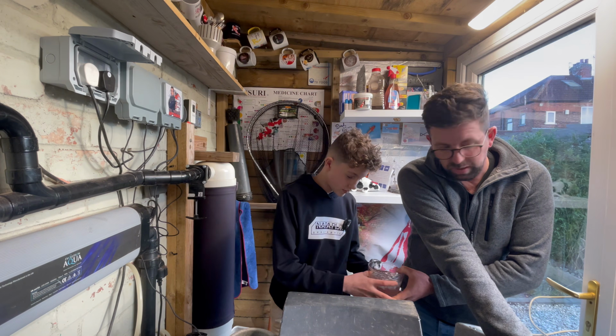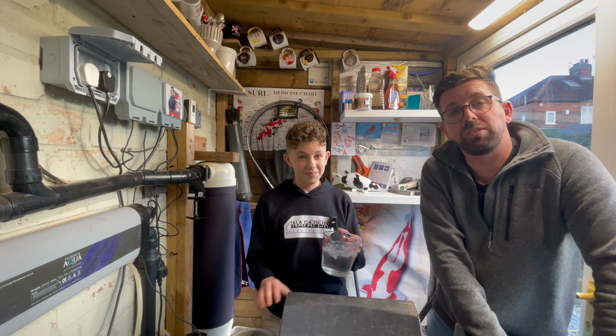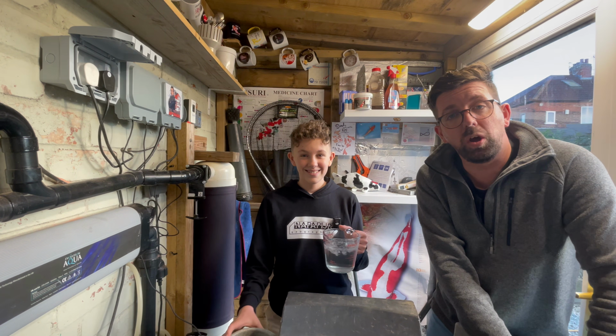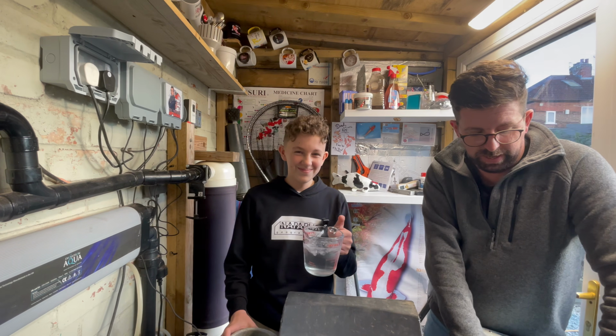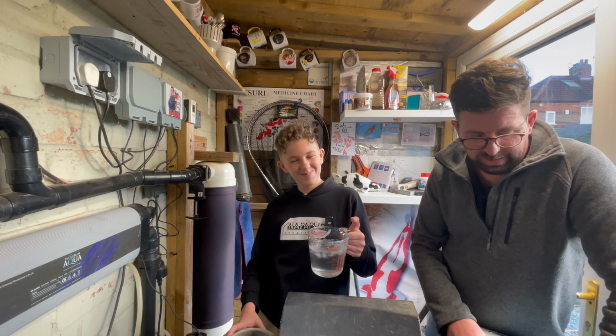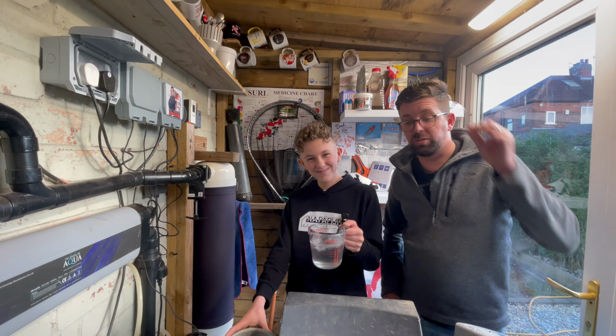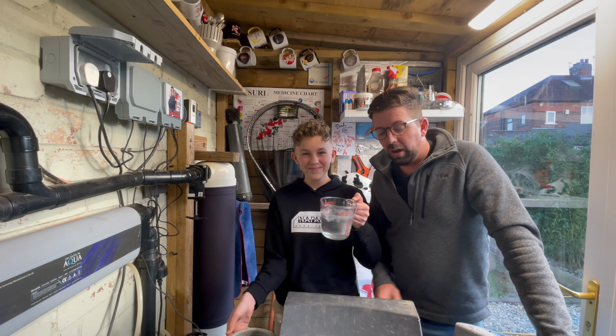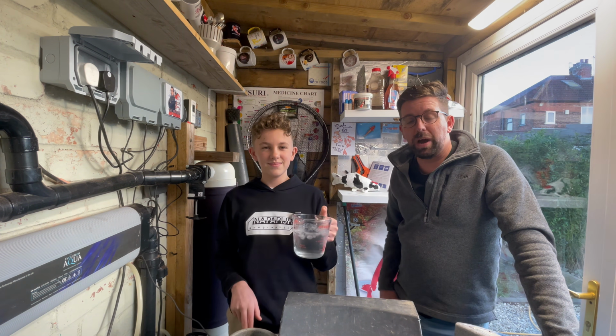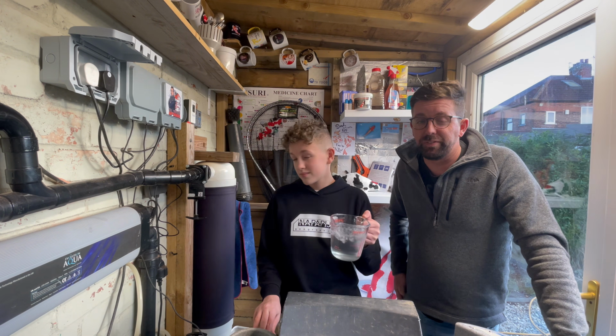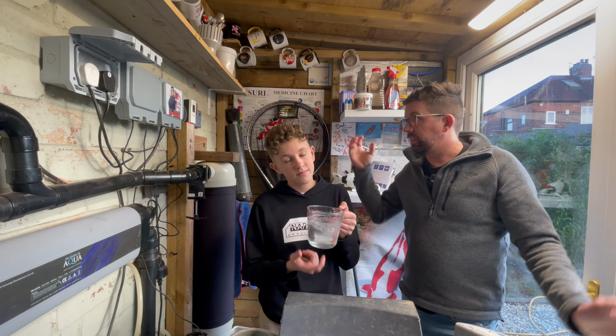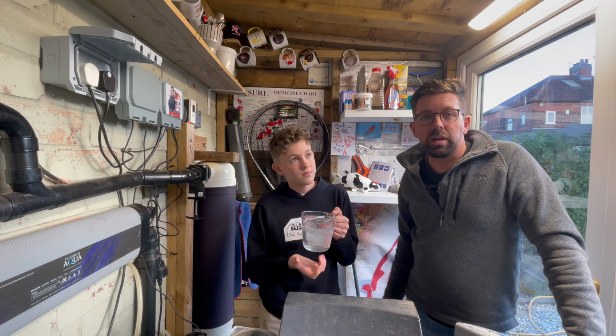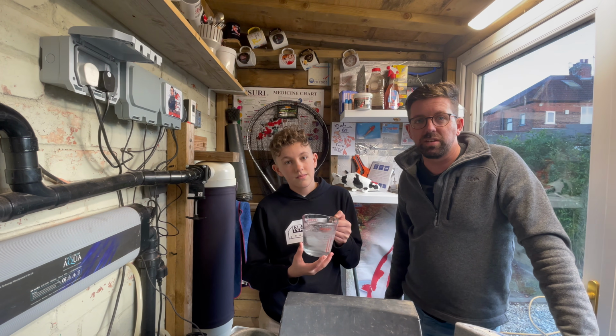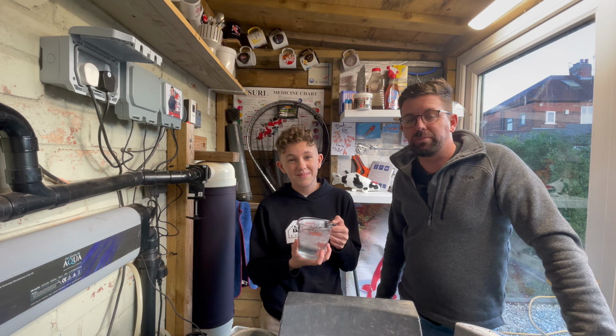All the other parameters are there as well, so you can set high, low pH, ORP, all of the salinity. You can set everything that you need to. So that just shows you there, and it also works if you lose power. I believe the loss of power alert is after 15 minutes. So if what it's connected to drops, it will send you a notification to say that it's offline, which is really cool.